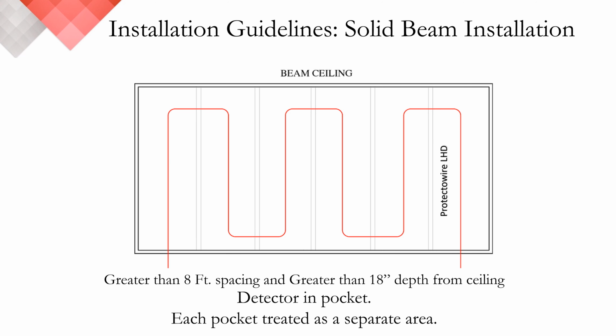In the case when solid beams are spaced greater than 8 feet, or roughly 2.5 meters, on center, and the beams project greater than 18 inches or 46 centimeters below the ceiling, each bay formed by the beam shall then be treated as a separate area.